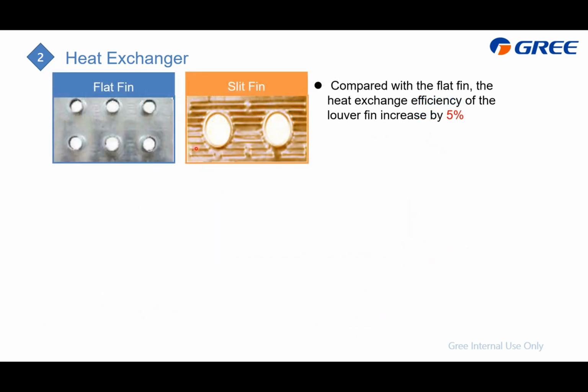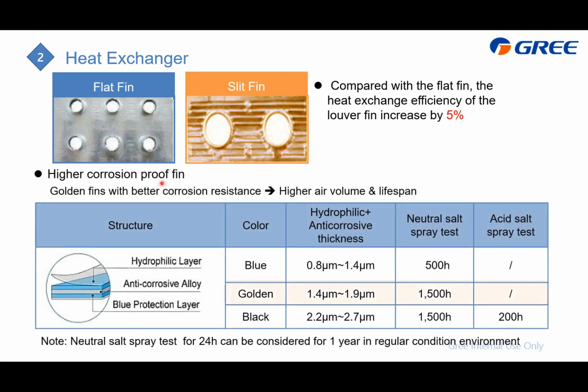Next is for the tubes and fins. First, for the fins, we adopt the slit fin. You can find that on the surface we have cut lots of slits to improve the heat transfer efficiency. And as for the anti-corrosion level, in our design we divide the anti-corrosion level by colors, which is blue, golden, and black.